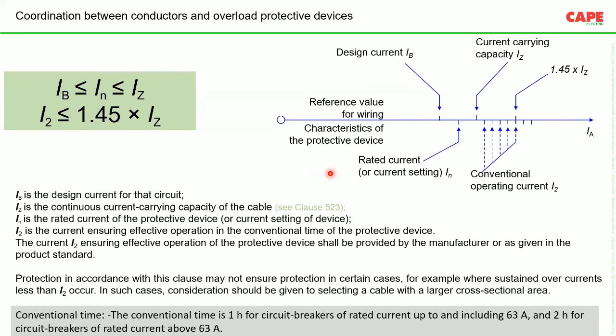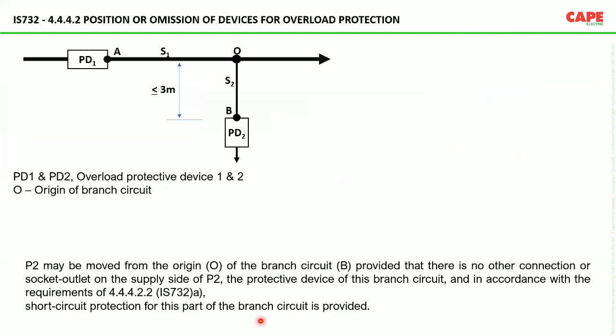So the correct way of using protective devices: first of all, the protective device is to protect the circuit. In order to protect the circuit, the first item on the circuit is the wire. So the device should be selected based on the wire size. And here you must understand that every protective device has a conventional disconnection time and conventional disconnection current. Conventional disconnection time is up to 1 hour. Conventional disconnection current is 1.45 times.